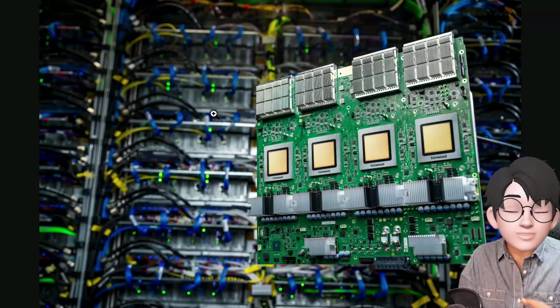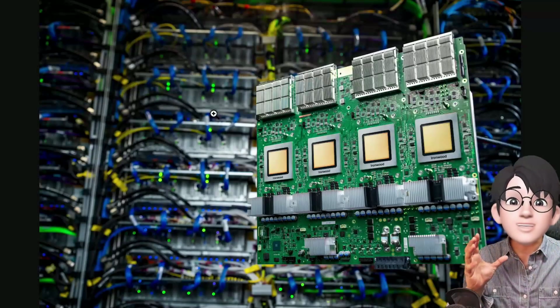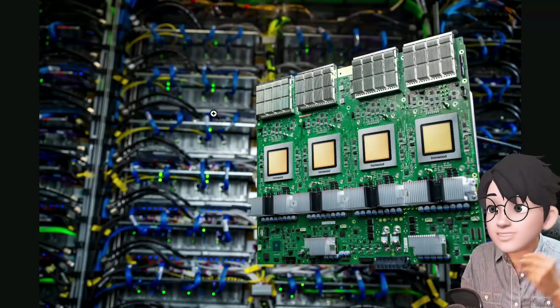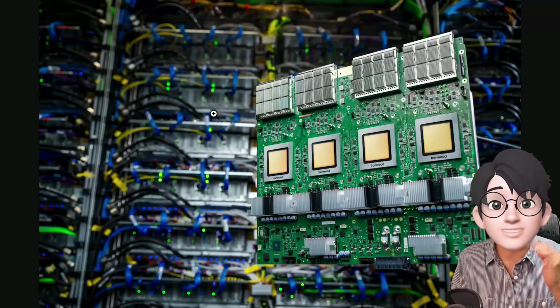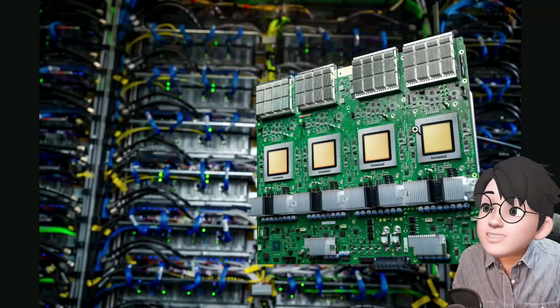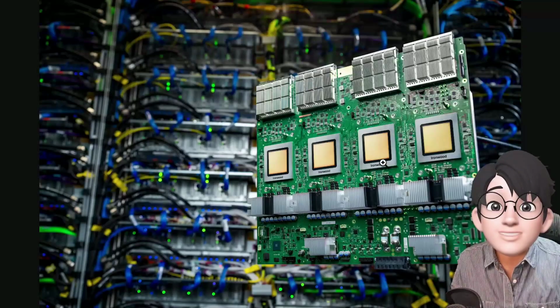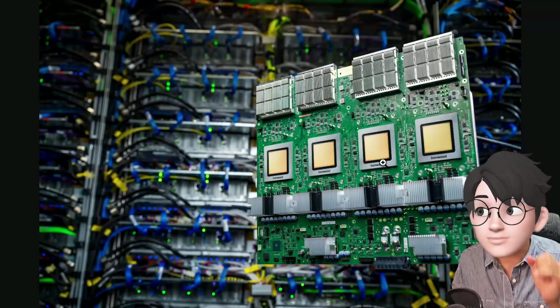That said, switching to immersion cooling allows for significantly better heat dissipation, as it involves fully submerging the chips in oil. To design such a structure, the data center building needs a complete redesign. When leveraging existing data centers, liquid cooling is the necessary interim solution. Therefore, in the case of Ironwood, it should be understood that it is utilizing liquid cooling rather than immersion cooling.